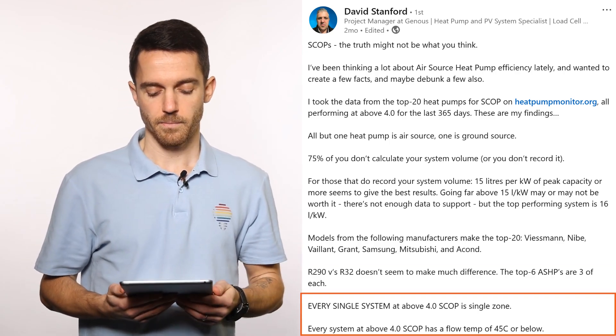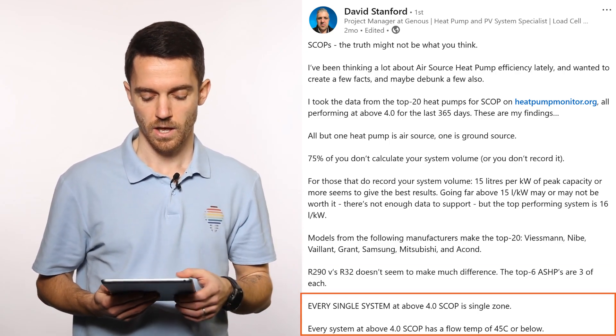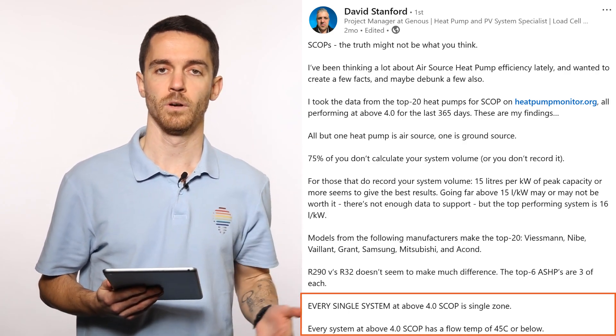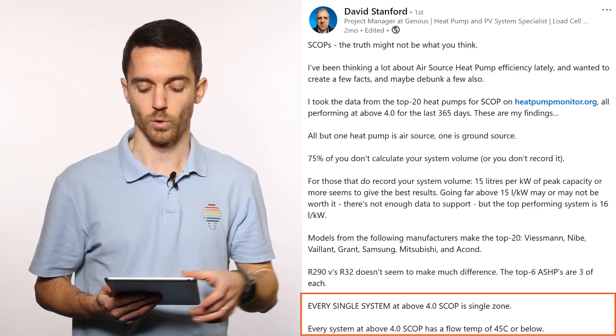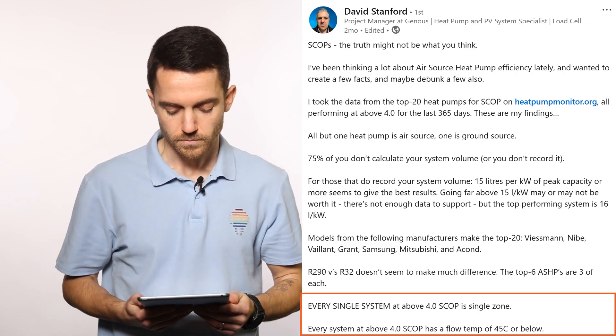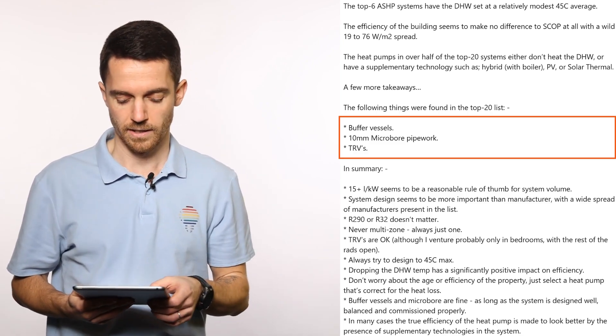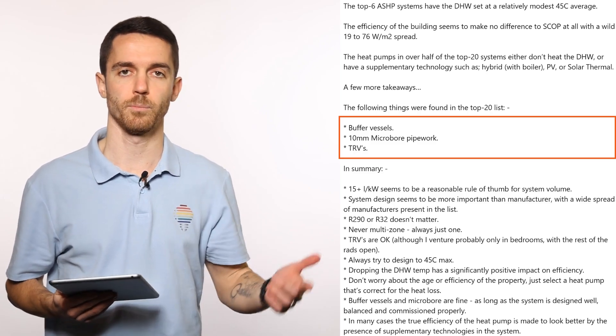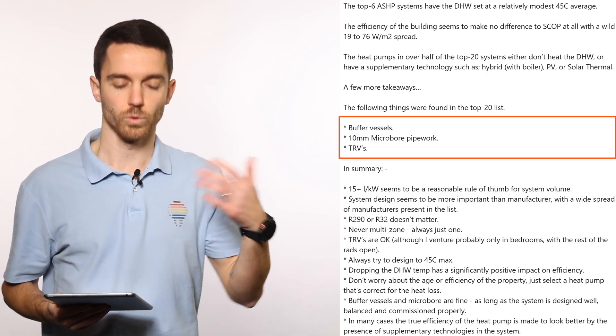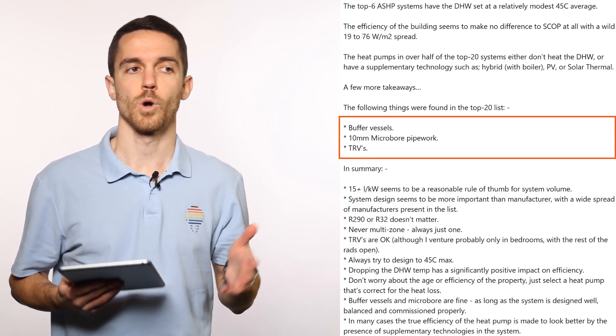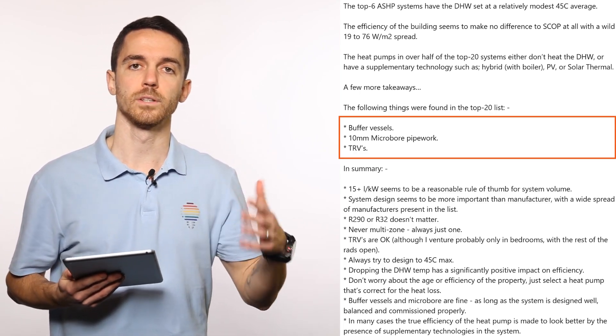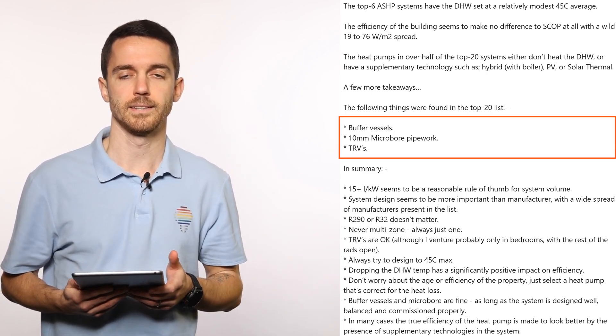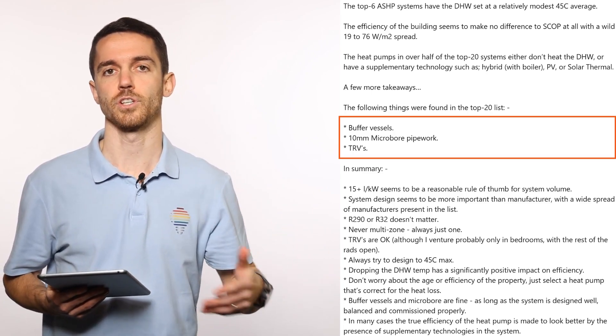Every single system with a SCOP above 4 is single zone, and every system with a SCOP of 4 and above has a flow temperature of 45 degrees or below. A few other takeaways: you can find buffer vessels, microbore 10mm pipe, and thermostatic radiator valves in these systems — all things we usually think cannot work efficiently with heat pumps.